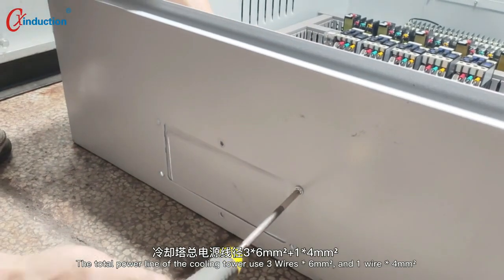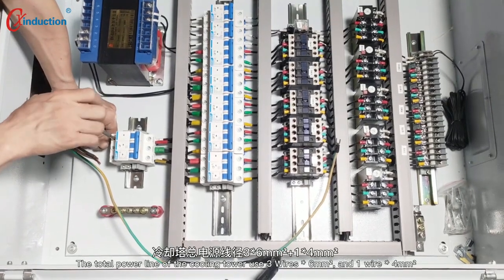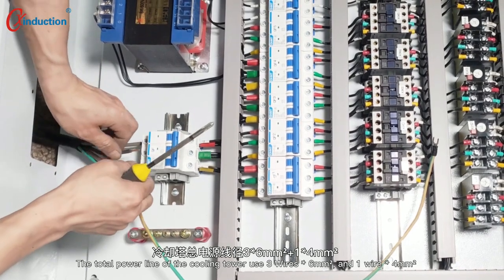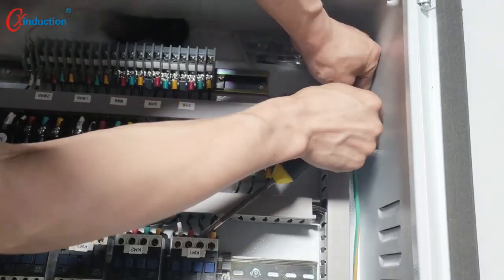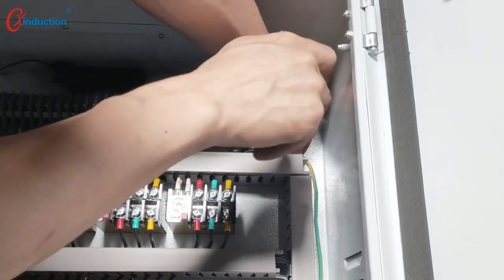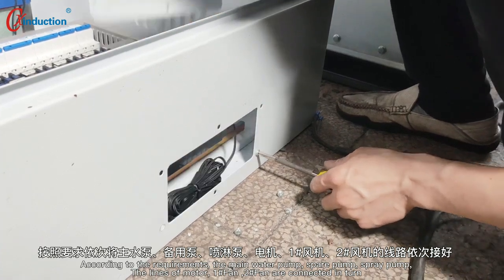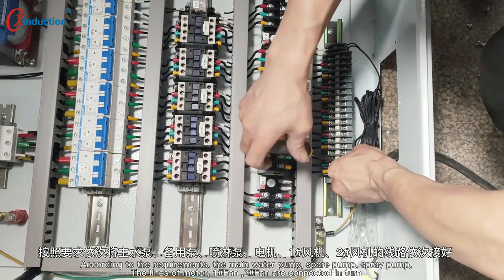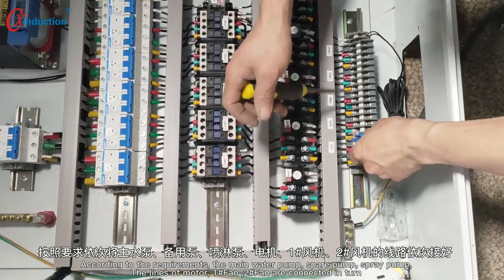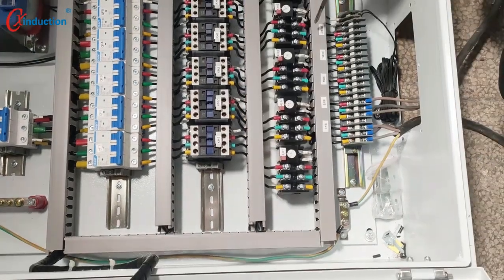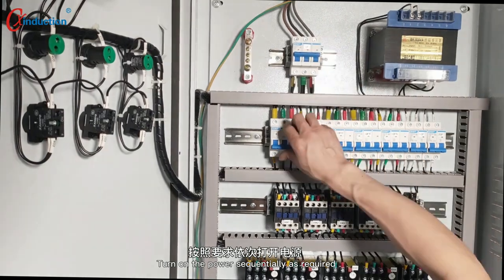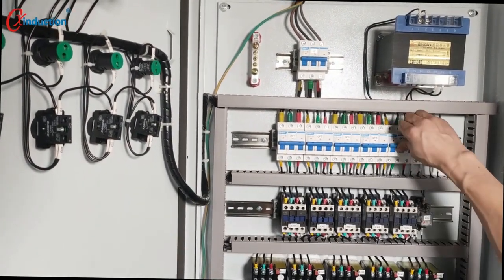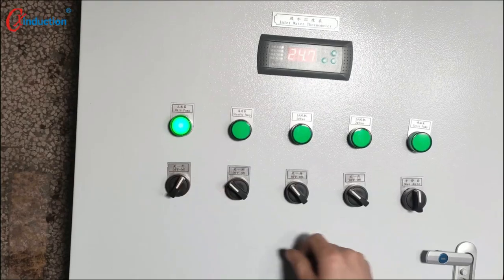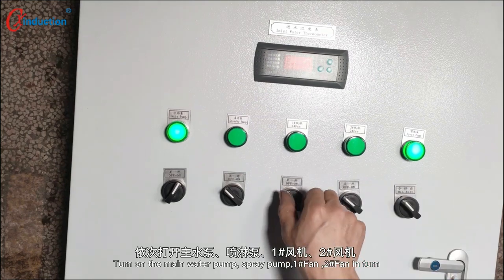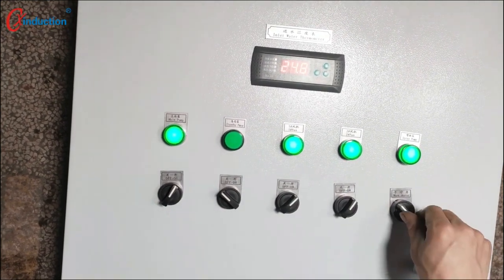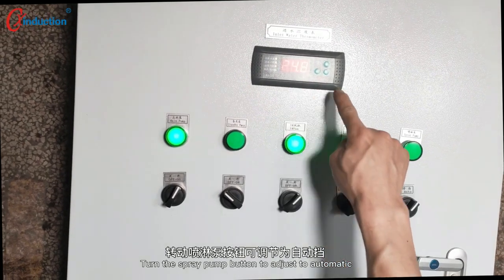The total power line of the cooling tower uses 3 wires with 6 square millimeter and 1 wire with 4 square millimeter. According to the requirements, the main water pump, spare pump, spray pump, the lines of motor, fan 1, fan 2 are connected in turn. Turn on the power sequentially as required. Turn on the main water pump, spray pump, fan 1, fan 2 in turn. Turn the spray pump button to adjust to automatic.